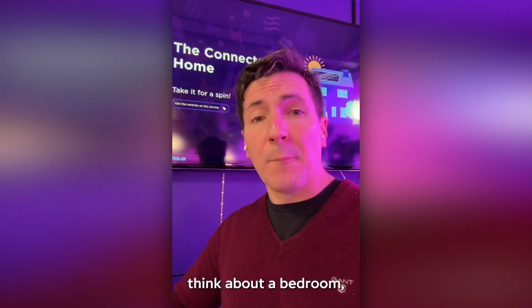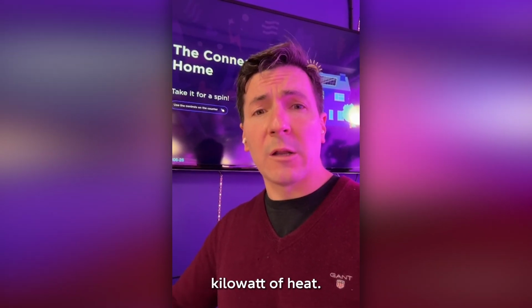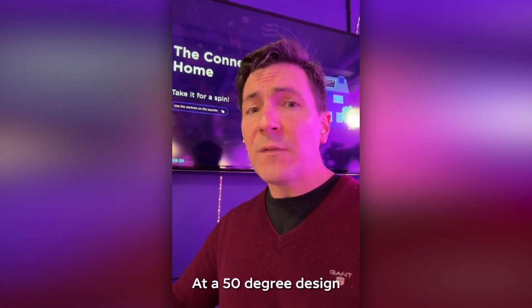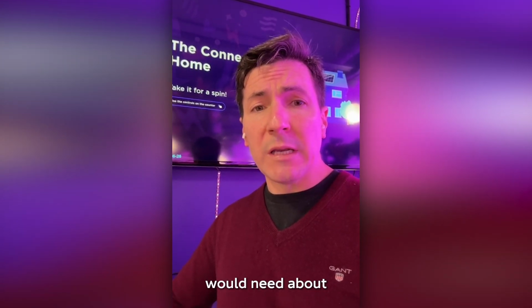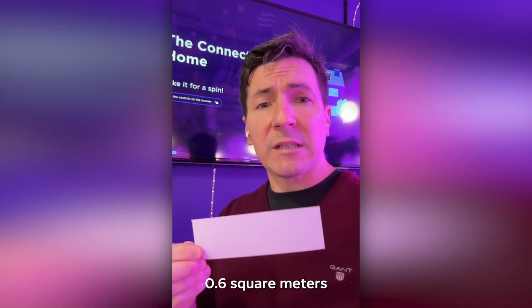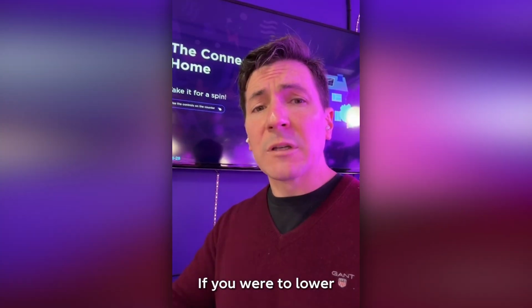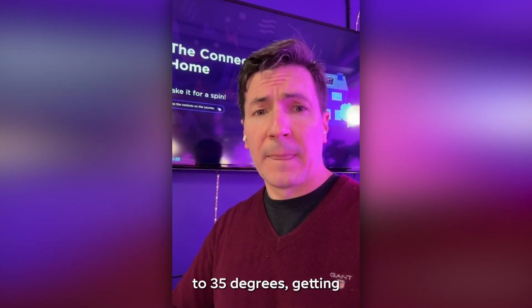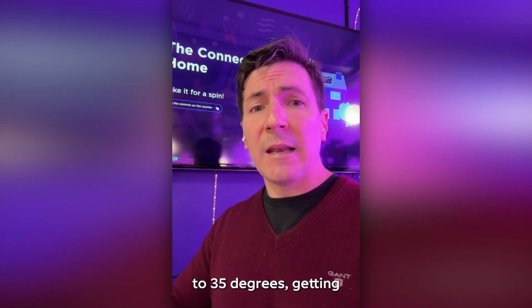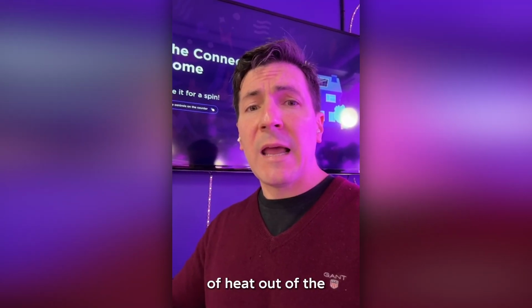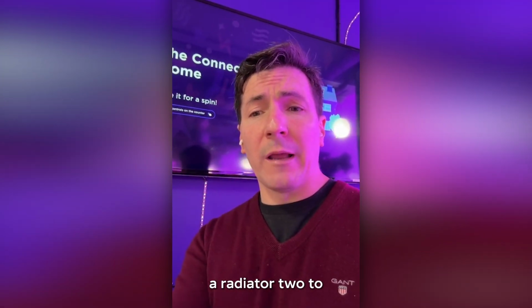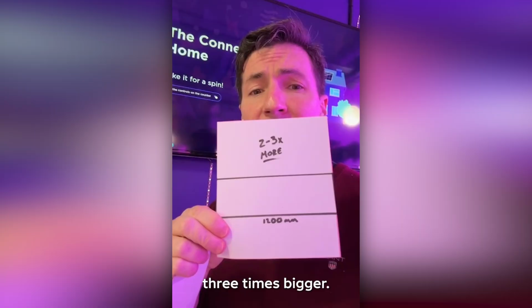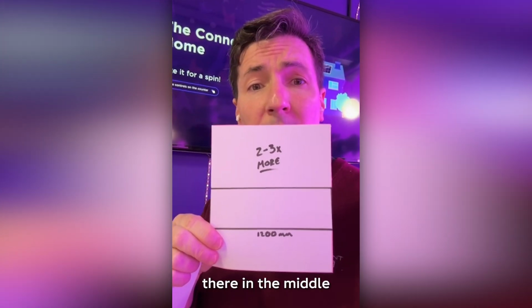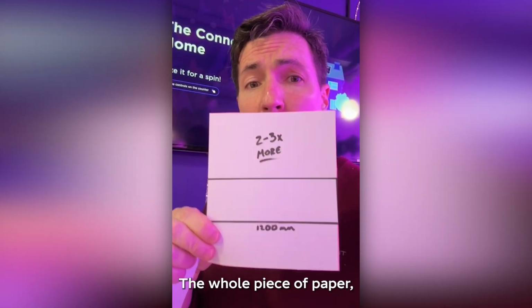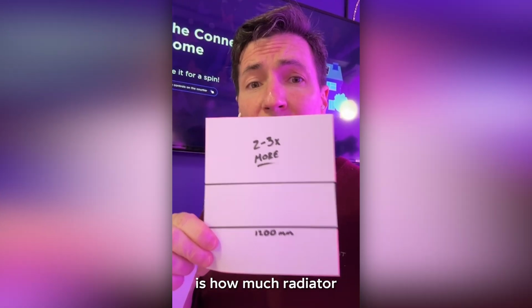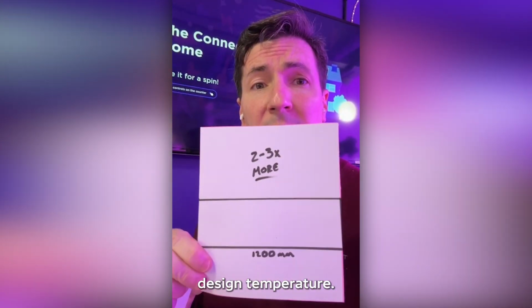So if we were to think about a bedroom where you needed 1 kilowatt of heat, at a 50 degree design temperature, you would need about 0.6 square meters of radiator. If you were to lower that design temperature to 35 degrees, getting that same 1 kilowatt of heat out of the heat pump would require a radiator 2 to 3 times bigger. So that rectangle there in the middle represents the one I just showed you. The whole piece of paper is how much radiator you'd need at that lower design temperature.